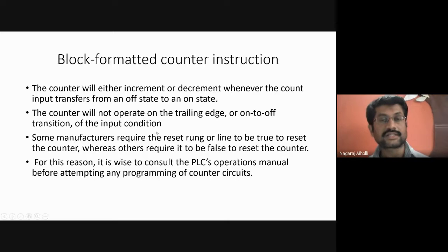Some manufacturers, and this is an interesting point, require the reset rung to go from false state to true state to activate the counter. Some manufacturers program it in such a way that for the true to false condition of the rung, the counter instruction is activated. It depends on the manufacturer. Siemens may manufacture in a different way. Allen Bradley may manufacture in a different way. Different manufacturers can manufacture in different ways.